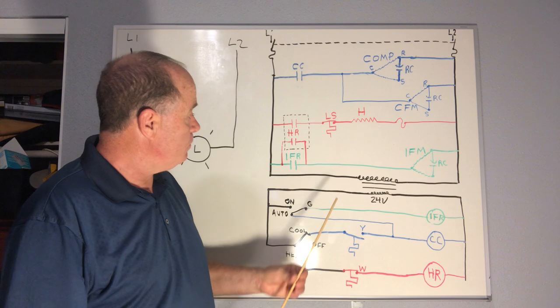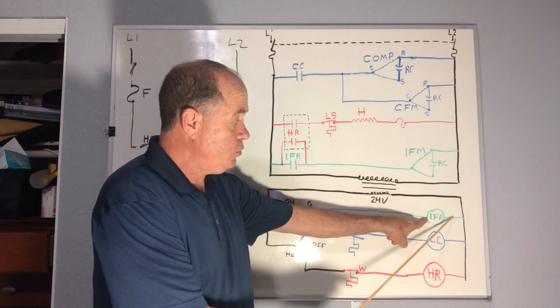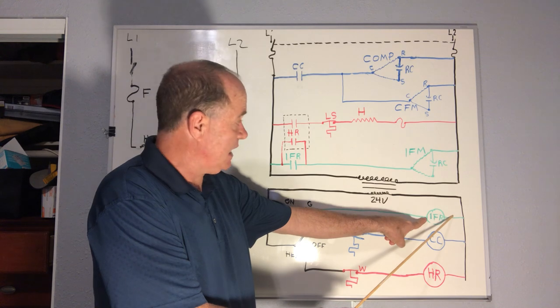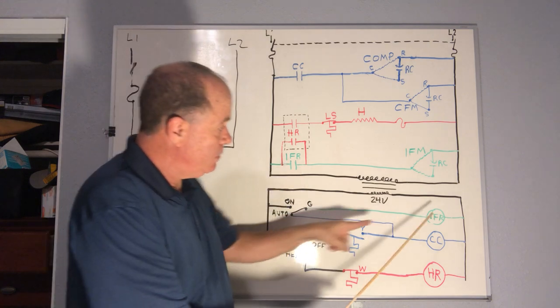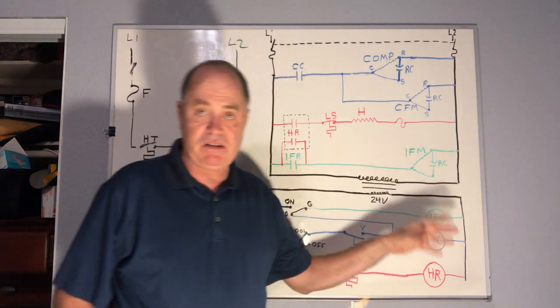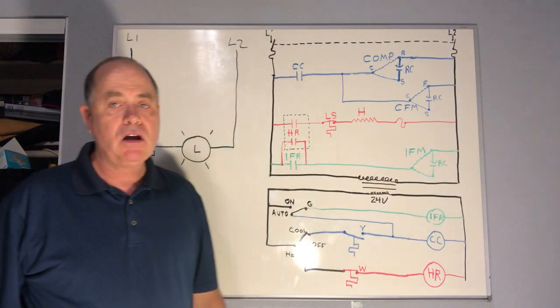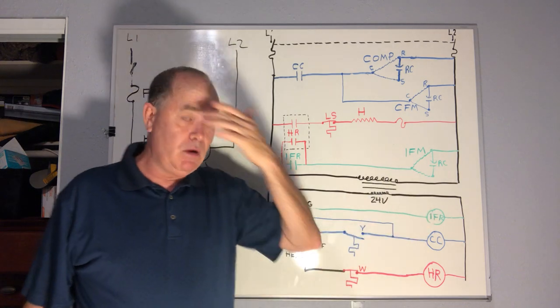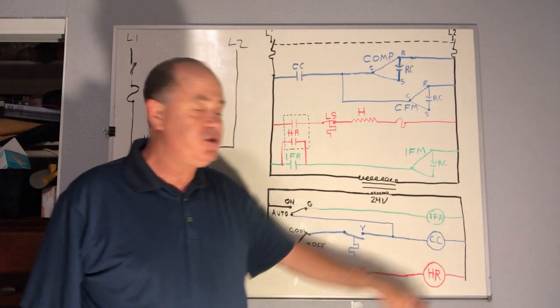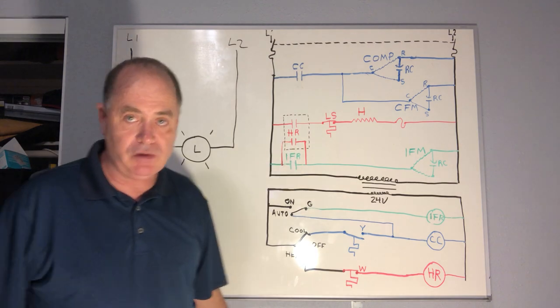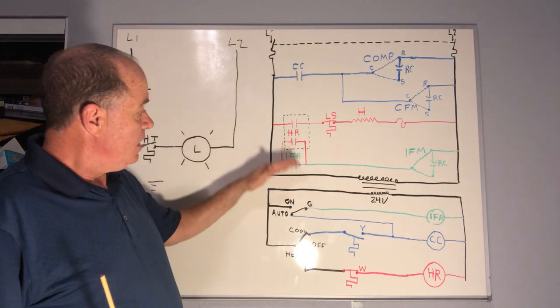If the fan wasn't running and we measured 24 volts at the indoor fan relay but the contacts weren't closing, and we didn't have 230 volts at the motor, we could assume the indoor fan relay is bad. We could ohm out the coil and try to replace it. Most likely the problem is the indoor fan relay if you're getting voltage to the coil but the contacts are stuck open — then we would replace that.